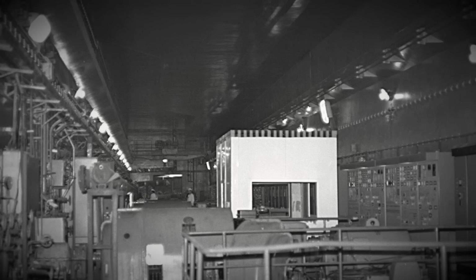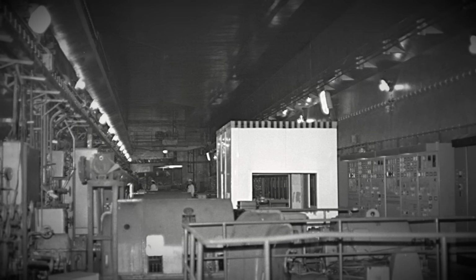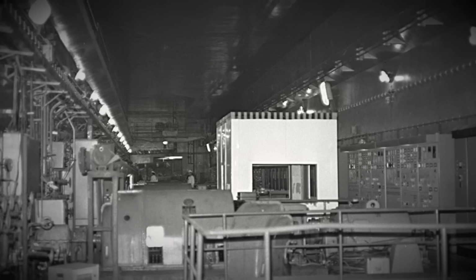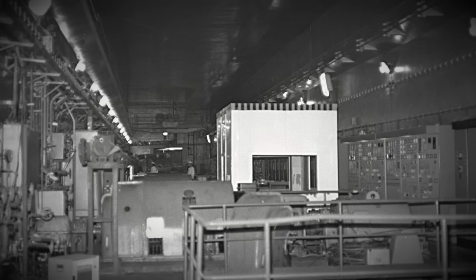With the reactor now losing coolant at a rate of 70 kilograms a second, the unit was in very real possibility of overheating, leading to a radiological disaster. The heat in the core was rapidly rising, and due to the reactor being shut down from the earlier power grid blackout, not enough electricity was available to pump the coolant. The site's diesel generators started up to push the coolant through the core, however some of the turbo compressors failed to start, thus stopping the flow of the coolant.